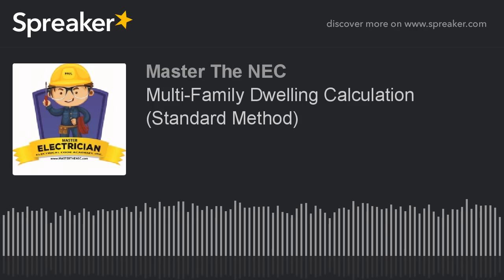We determined also that each one of these units obviously has to have an air handler because it has a motor, and it's what's pushing the air out, whether it's cooling or heating. So in our equation, we actually gave you an air handler value. In our case, the air handler was a 0.5 horsepower. So we have to do the same thing that we just did. We have to go to table 430.248, and we find a 0.5 horsepower.